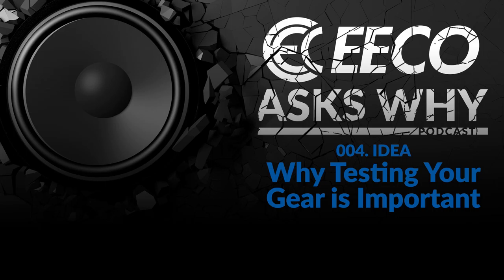And so that's part of this as well, making sure that all breakers are rated appropriately. So that kind of covers short circuit and coordination studies. Arc flash studies, you want to make sure that you understand the available arc incident energy at each point in your electrical system. That has to do primarily with personnel protection, making sure that each of your employees that might be working in or around that equipment will not be exposed to high arc energies. And if they are, they would be donning the appropriate PPE or staying outside of some limited approach boundaries, which we've spent some time talking about in other podcasts. So arc flash hazard analysis gives us that information.